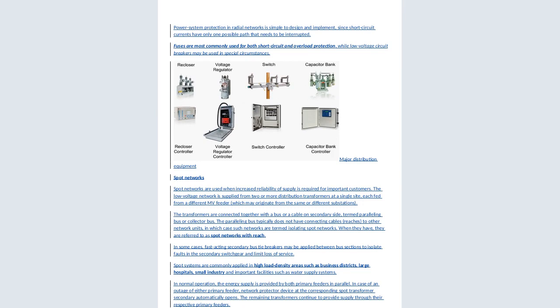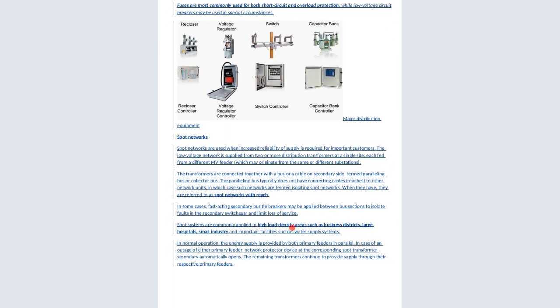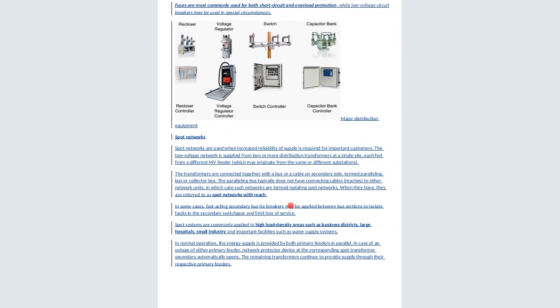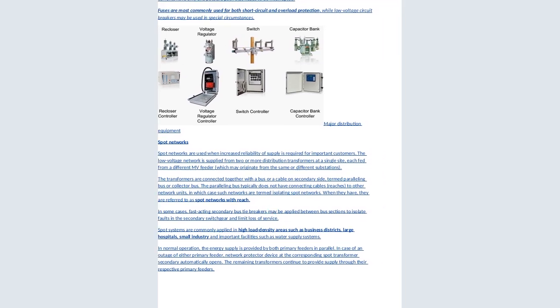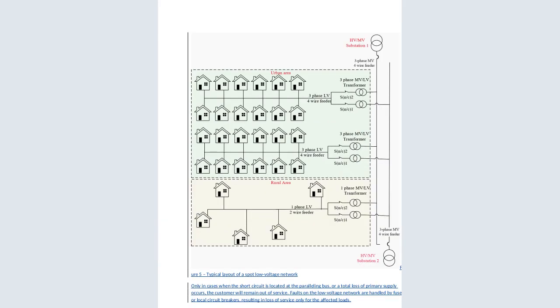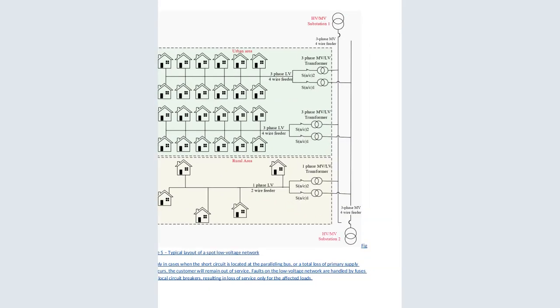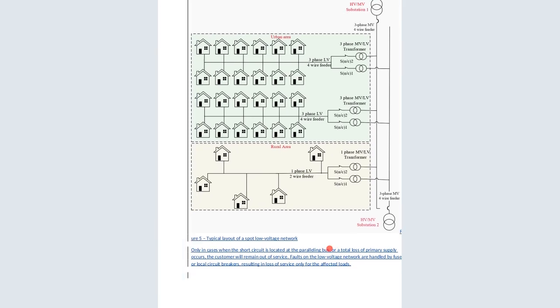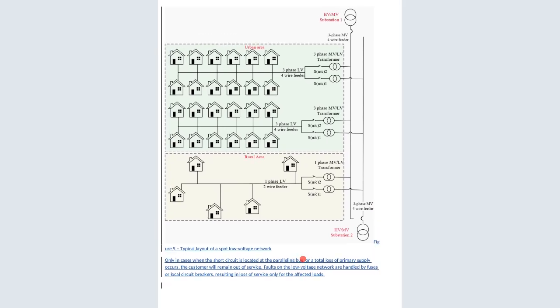You can see now the major distribution equipment. We have a recloser controller, voltage regulator controller, switch, these are big switches, switch controller, capacitor bank, and the capacitor bank controller. Spot networks, we had talked about the spot networks, and we said that they are used when increased reliability of supply is required. That is how the spot network is distributed. This is a typical layout of the spot network, because this one has less interruption of power.